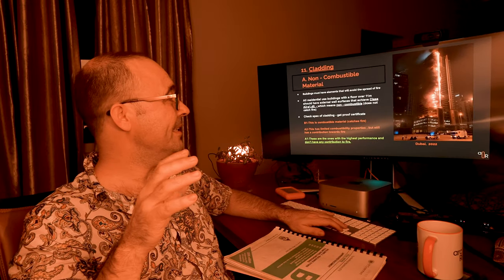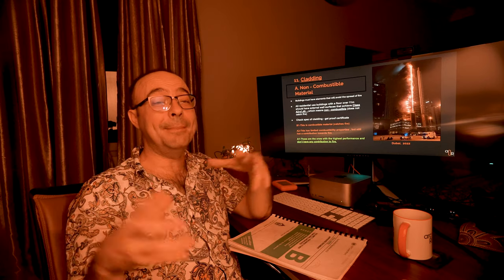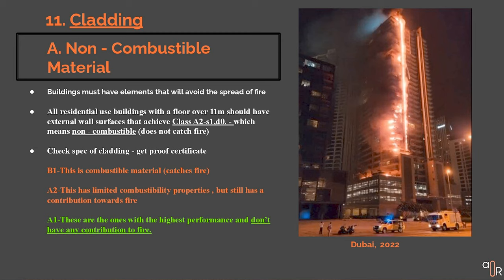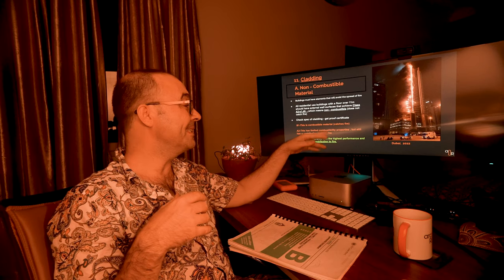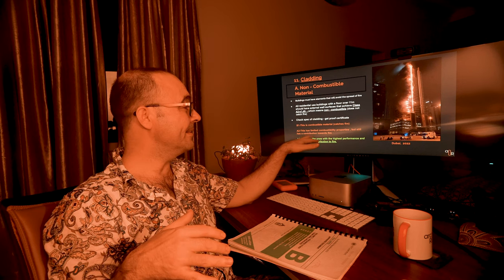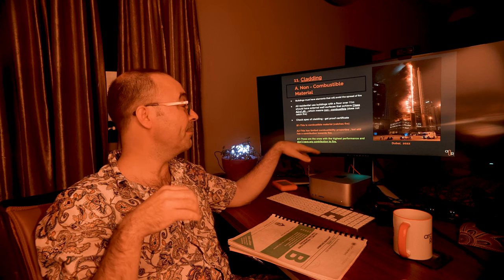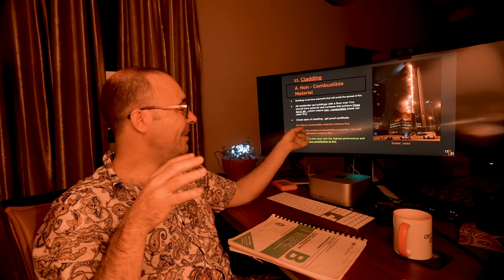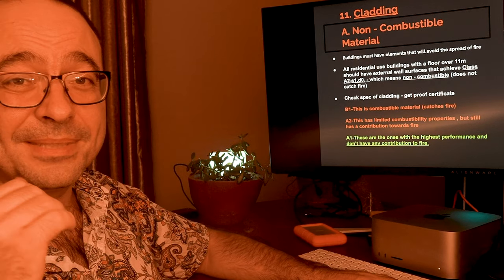I'll briefly touch on cladding. When you have a building over 11 meters, the material of the cladding needs to be non-combustible — it can't catch light. It doesn't mean it's fire resistant; it means it doesn't spread fire. You have ratings like B1, which is combustible, meaning it's flammable — that's the aluminum cladding type famous from Grenfell. A1 and A2 mean limited or no flammability. A1 is the best — not combustible at all. They say A2 is acceptable, but I would only use A1. Whatever you use for cladding, you've got to make sure it's non-combustible.